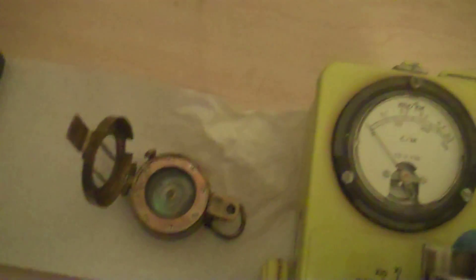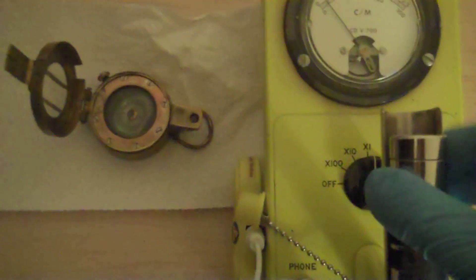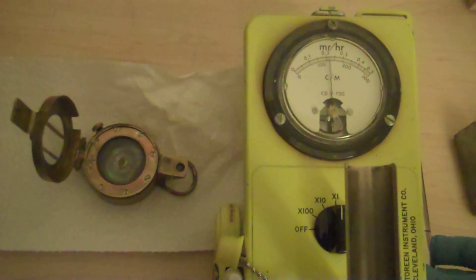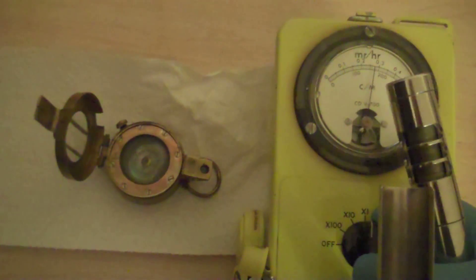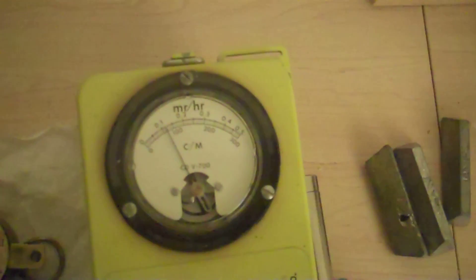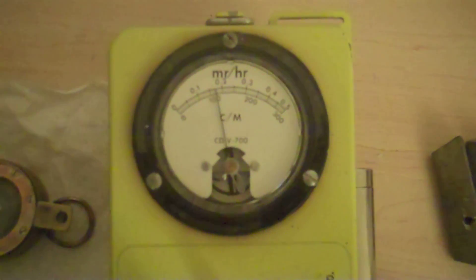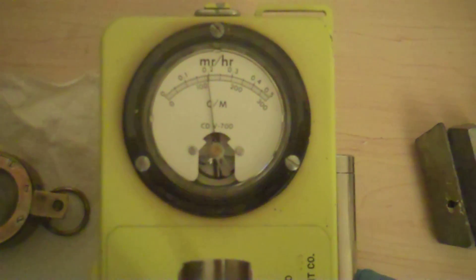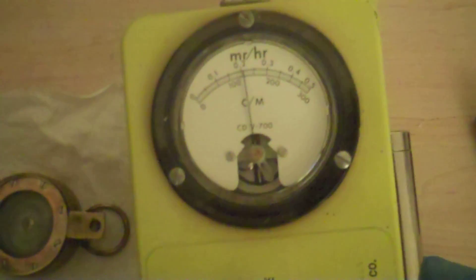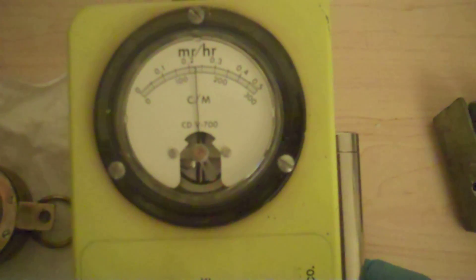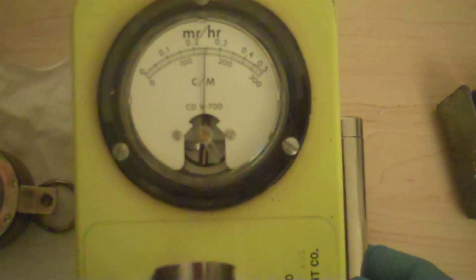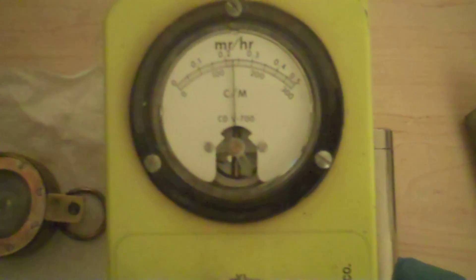Using my old CD V-700 here, we'll cut that on. The beta shield's open. We'll put it on the tester. It's definitely working. We'll put it on times 10 and hold it up against the check source on the side. And see that it shows about 2.5 milliroentgen per hour, which means that we know it's working and that it's calibrated.